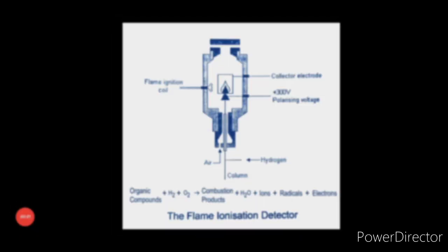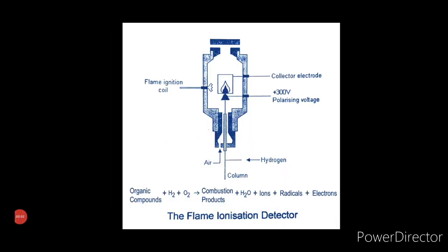Flame ionization detector. Let us understand the function of detector first. The function of detector is to sense and measure the separated components in the carrier gas flow leaving the column. The choice of detector depends on the nature of the sample and the level of analysis. Flame ionization detector is generally used because of its high sensitivity.